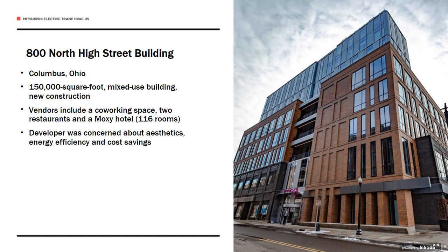The 10-story, 150,000 square foot mixed-use building at 800 North High Street was recently opened in the Short North Arts District of Columbus, Ohio. It houses two restaurants, an upscale hotel, and co-working space in this trendy neighborhood. Due to the conditioning needs of the diverse tenants, selecting an HVAC and ventilation system was a challenge for the owner. The wide-ranging tenants demanded energy efficiency and differing levels of ventilation based on how their particular space was being utilized. In addition, aesthetics were very important to the developer, the county, and the hotel brand occupying the building.